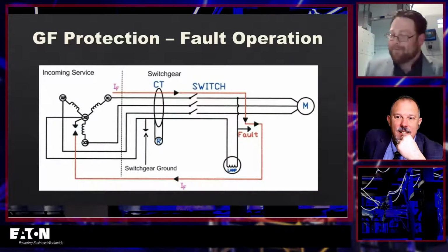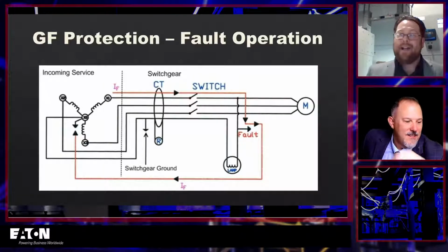Wow. Talking about another example, you got my mind going here. I was out of town a few weeks ago at a chemical plant, and they had installed brand new switchgear with a high resistance grounding detection system in it. They purchased all the bells and whistles, so they had indicating lamps to tell you which phase the ground fault was on. How that system works is your three lights are normally on, which means you have no ground fault. If one light goes out, that's the phase you have a ground fault on.